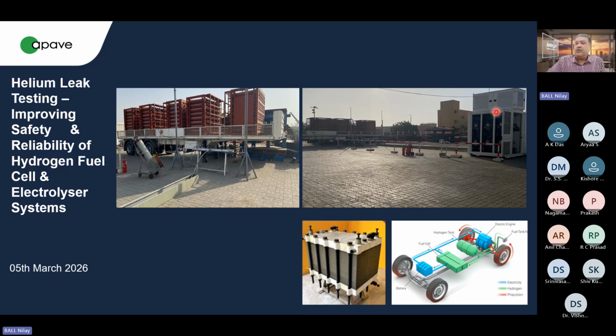So in the morning, we shut down the systems, and then we tested it with normal air or with nitrogen, and we couldn't find the leakages. And then we started testing it with helium. There was no helium leak test mechanic in this part of the Middle East. So we had to fly back to India, take the helium leak test equipment, go back there and test the helium leakages.